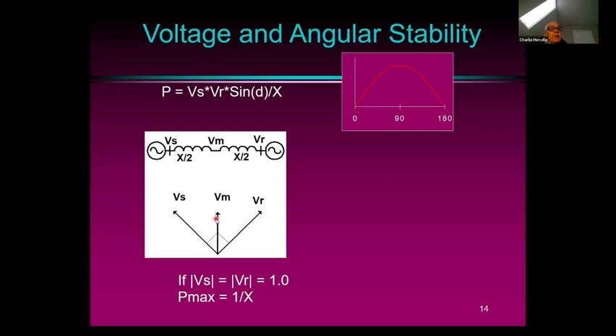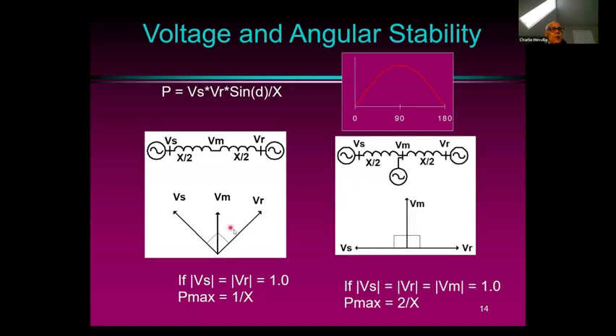But we notice that the voltage in the middle is somewhat less than 1 per unit. So if we just boost the voltage in the middle by adding capacitors or reactive power, no real power coming in at this generator, but just boosting the voltage, we see all of a sudden we can deliver twice as much power through the same transmission system. So there's our reactive power doing its job to support the power system and allowing more power to be transmitted.